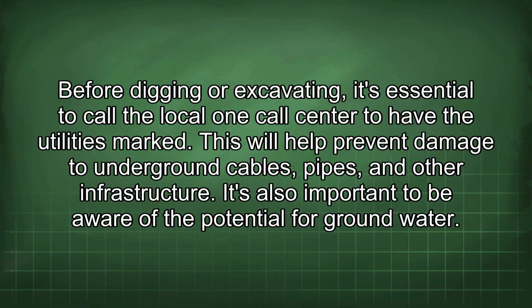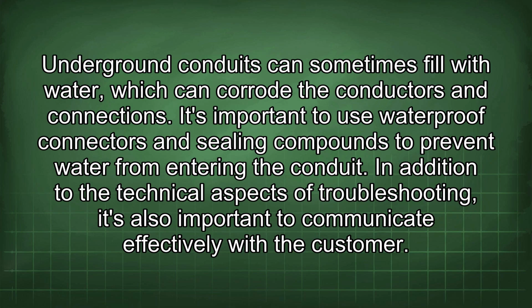utilities. Before digging or excavating, it's essential to call the local one-call center to have the utilities marked. This will help prevent damage to underground cables, pipes, and other infrastructure. It's also important to be aware of the potential for groundwater. Underground conduits can sometimes fill with water, which can corrode the conductors and connections. It's important to use waterproof connectors and sealing compounds to prevent water from entering the conduit.